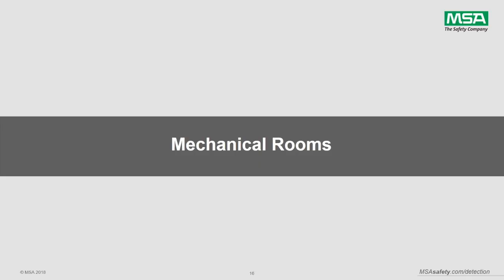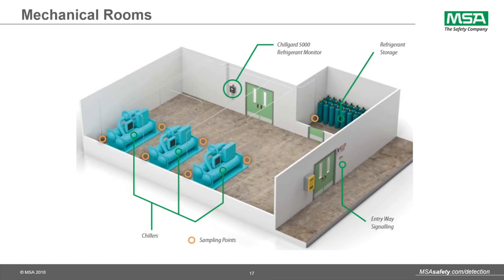Moving into the application portion, we will focus on safety within mechanical rooms. For a mid-sized commercial building, 2 to 3 chillers is common for cooling a space that size. In this diagram, we show 3 chillers, each being monitored for refrigerant leaks. The most cost-effective refrigerant leak monitor is a sample draw system. This is where the central panel pulls in a sample from various lengths, and it's drawn through a sensor. This particular detector can take up to 16 different points back for sampling. The monitor can be mounted inside or outside the mechanical room using flexible tubing like polyurethane or a hard tubing like stainless steel or copper.